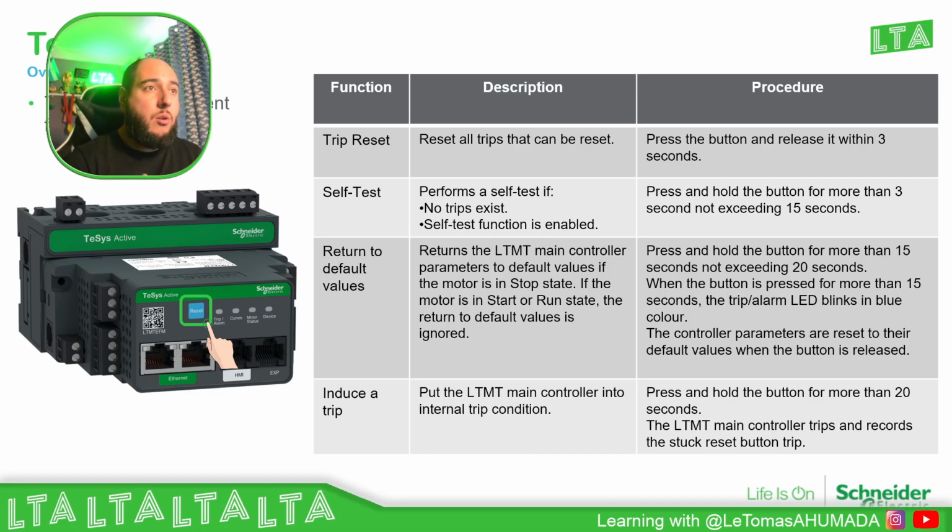Okay, the second one is a self-test, and you can execute it as long as there are no trips. The important thing is the duration of how long you're pressing this, because depending on that, you can probably go to another function. So when you go into the self-test, you just need to press between 3 and 15 seconds.